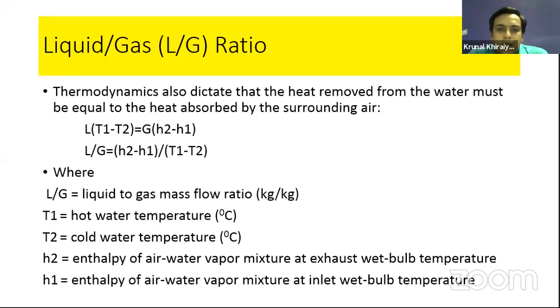But temperature has units of degrees centigrade, and the L/G ratio we are measuring in kg per kg. So here I am treating the units of enthalpy as kilocalorie per kg, and for temperature, the specific heat of water is 1. So we don't need to multiply by the Cp. Otherwise, if you are using kilojoule units, then you need to multiply by the Cp of water, which is 4.186 kilojoule per kg per degree. So here are the most important terms, please note them down if you want to remember. Otherwise, you can take it in kilocalories.